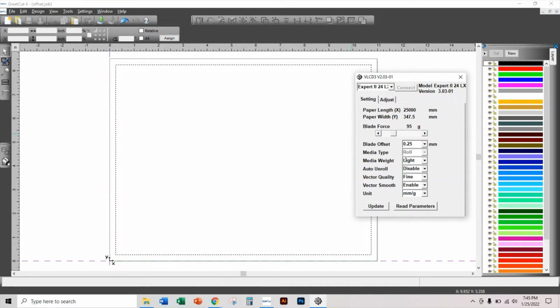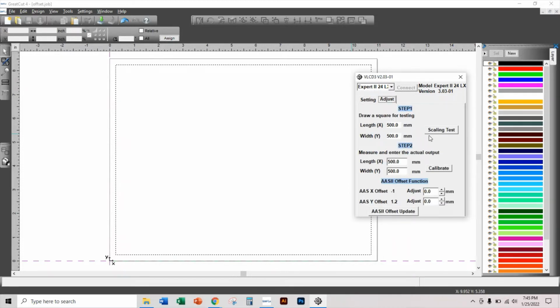Now, as you can see, when it connects, it gives you the parameters for your settings and then your adjustments. For the scaling test, this was done at the factory. They're supposed to draw a square that's 500 by 500 millimeters, and then they measure the actual output. On my machine, the length was actually 496 and the width was 500.8. Also the offset: my x-axis was -1, and my y offset was 1.2.